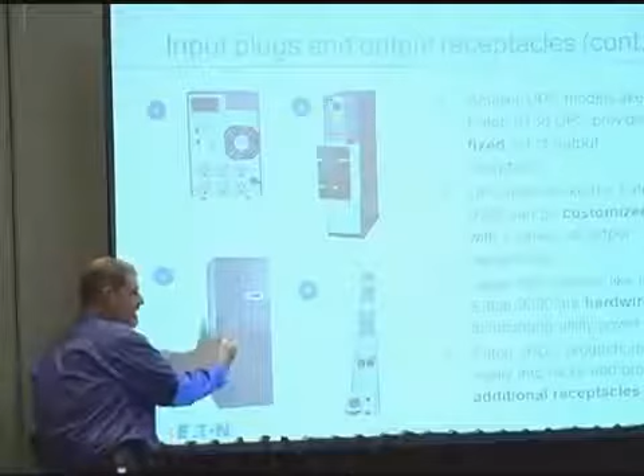We get into larger three-phase. Here we're talking about terminal blocks, right? Once I go beyond 30 amps or 50 amps, I have to go to a terminal block input. Question is, how do I convert the terminal block to receptacles? And I do that through distribution panels.